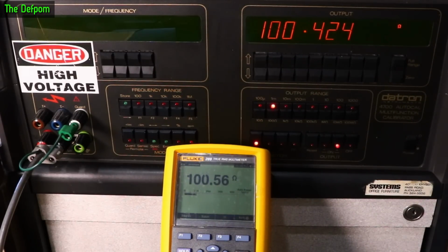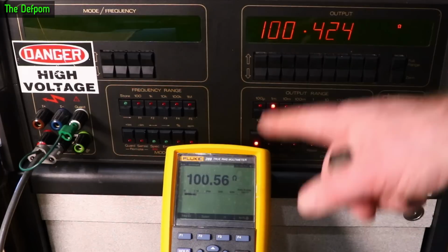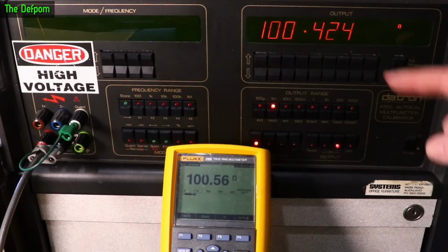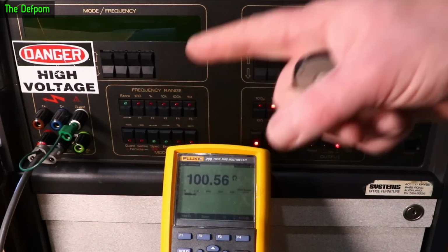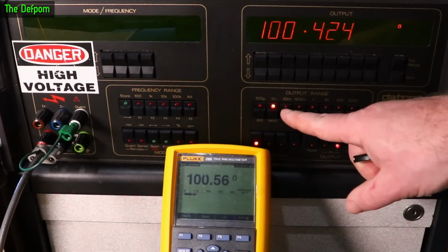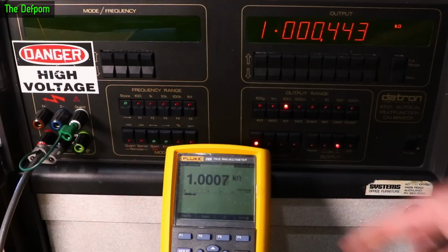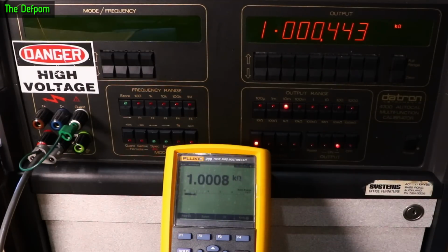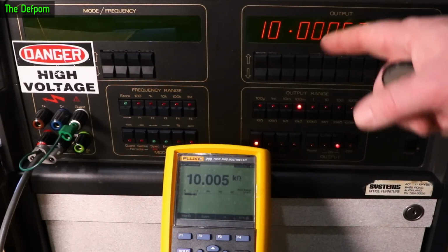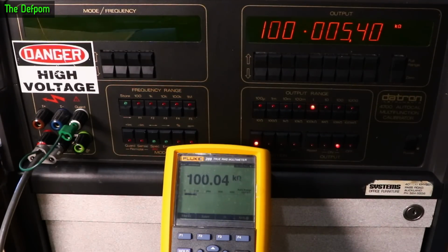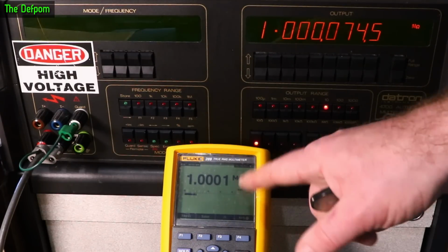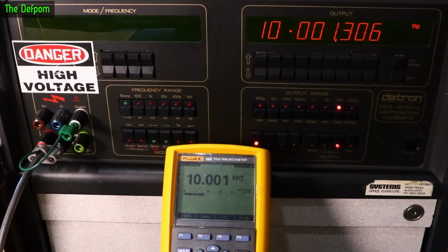Lead resistance. So, what was it, 0.13? If you factor that in, it's actually going to be about right. So if I actually shorted out the lead resistance and then did this test again, these would be basically bang on, I think. So 1k, again very slightly high here, not much. 10k is 5 counts up compared to the calibrator. That's actually surprising. So 100k is 4 counts up, 1 meg is basically right, it's 1 count out basically. 10 meg is basically right, 1 count, so it's actually looking pretty good there.